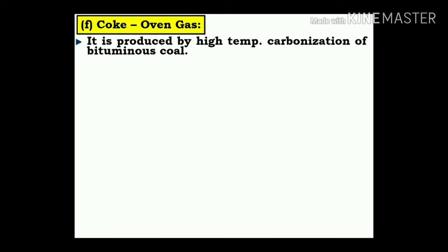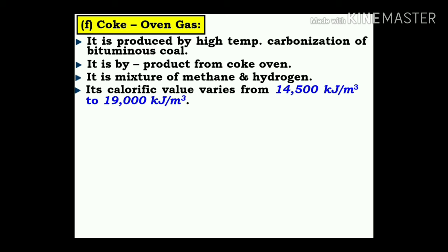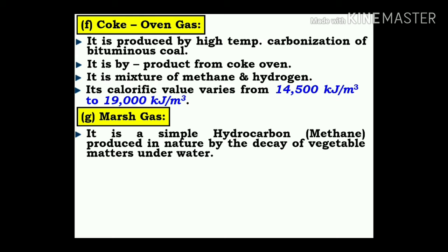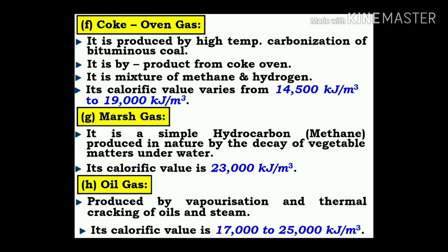Coke oven gas: it is produced by high-temperature carbonization of bituminous coal. It is a by-product of the coke oven, a mixture of methane and hydrogen. Its calorific value varies from 14,500 kJ/m³ to 19,000 kJ/m³. Marsh gas: it is a simple hydrocarbon produced in nature by decay of vegetable matter under water. Its calorific value is 23,000 kJ/m³. Oil gas: produced by vaporization and thermal cracking of oils and steam, with a calorific value in the range of 17,000 to 25,000 kJ/m³.